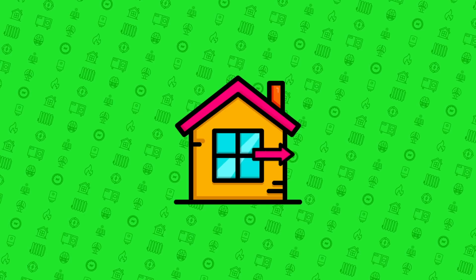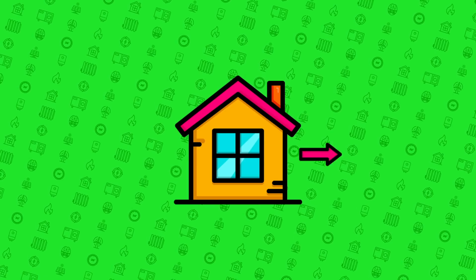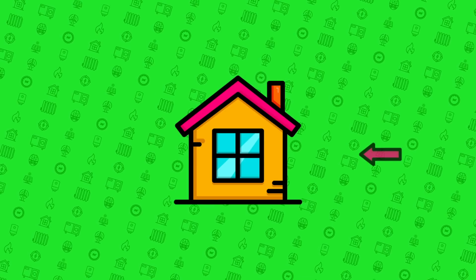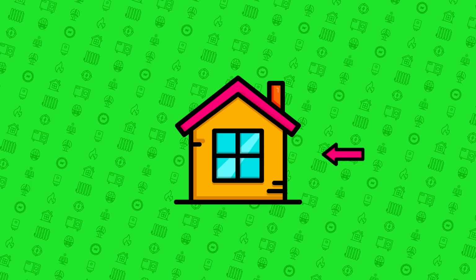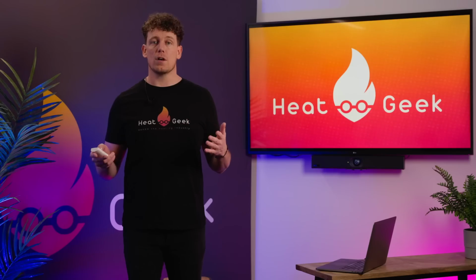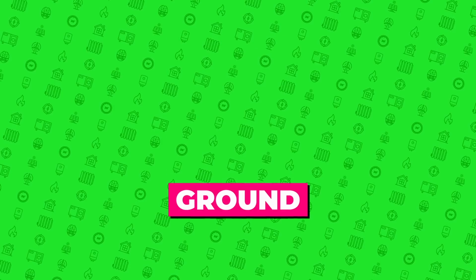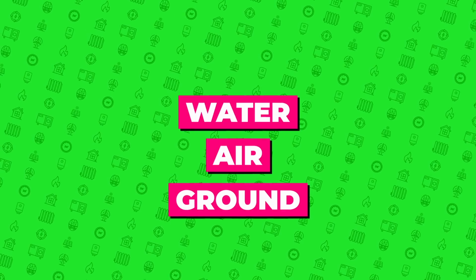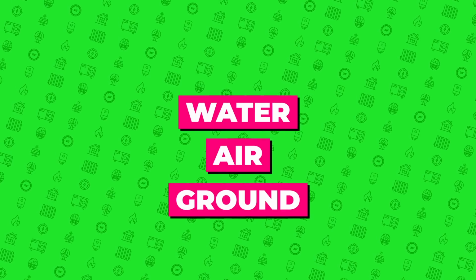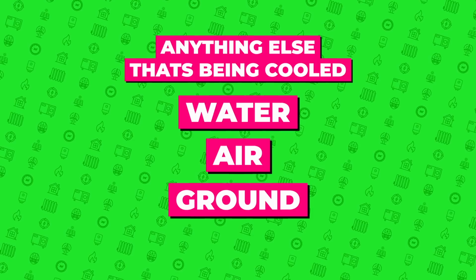Heat pumps simply move heat from A to B. If you're cooling the property, you're obviously moving heat from the inside of the property to the outside. When moving heat into the building, however, the actual heat source can vary. For example, you could source heat from the ground, air, water, or in the case of commercial properties, anything else that's being cooled, such as a server room or commercial fridge. By far the most common source of heat energy, or sink if cooling, is air.